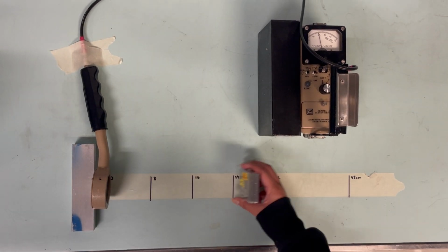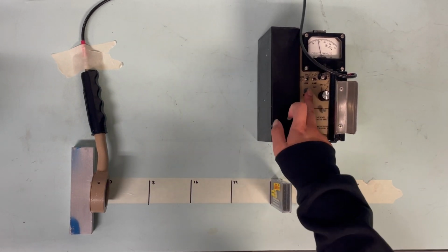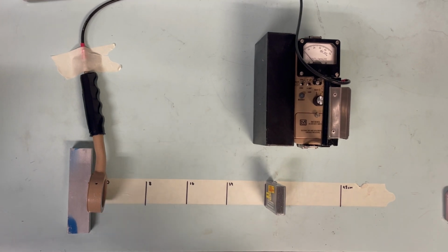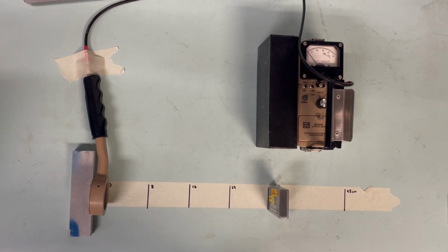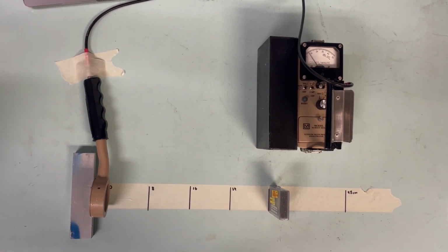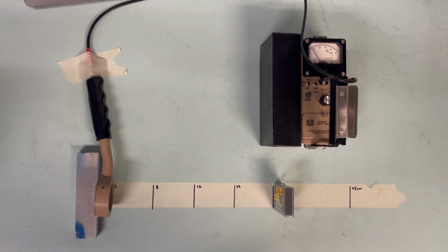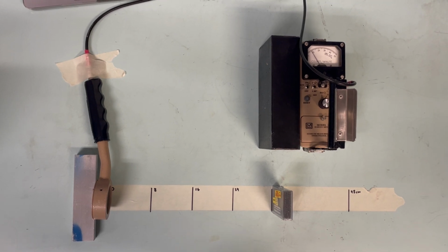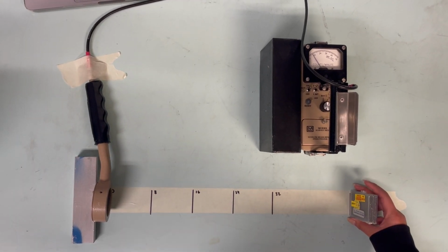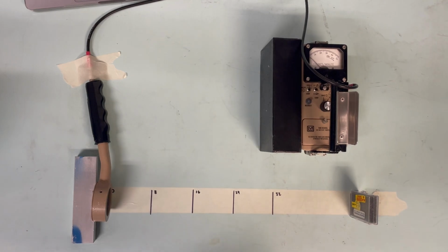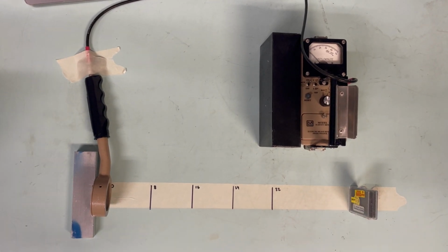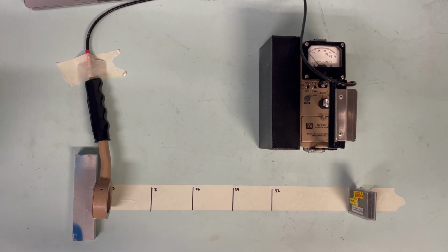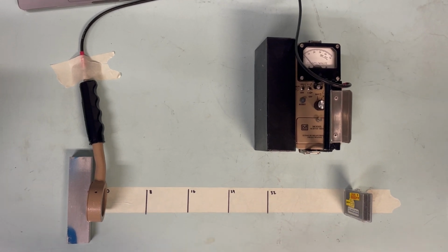And then from here, we're able to move it back to 32 centimeters. And after resetting it, we're able to read a level of 0.5 on the 1 scale. And again, once we move it back from 32 to 48 centimeters, we have to lower the scaling because the radiation has dropped off. And from this distance, we're able to read 1.9 counts per minute on the 0.1 scale.